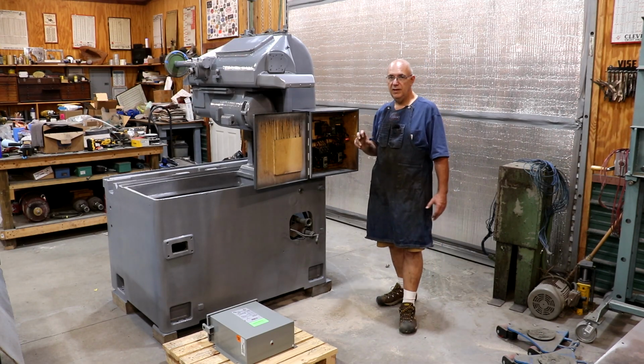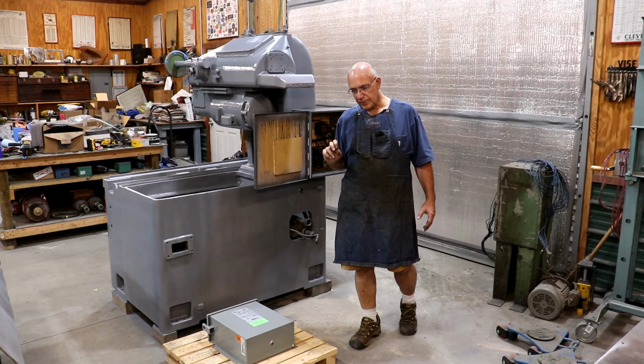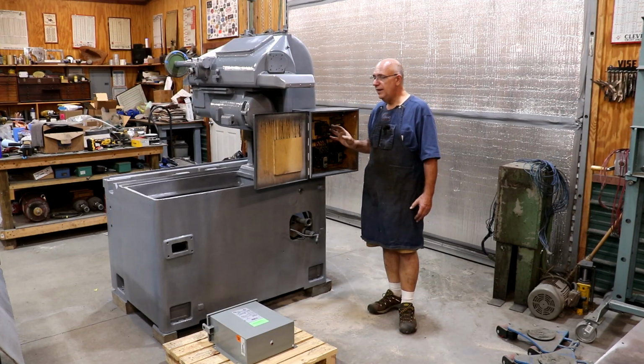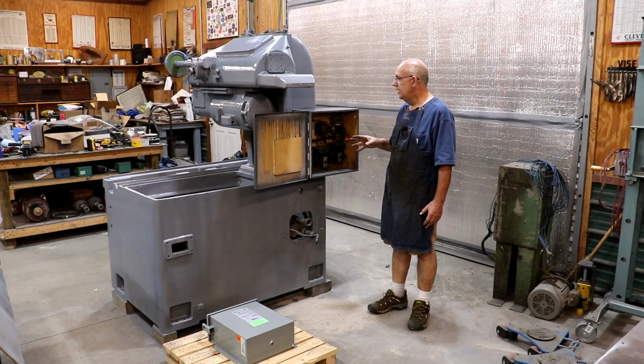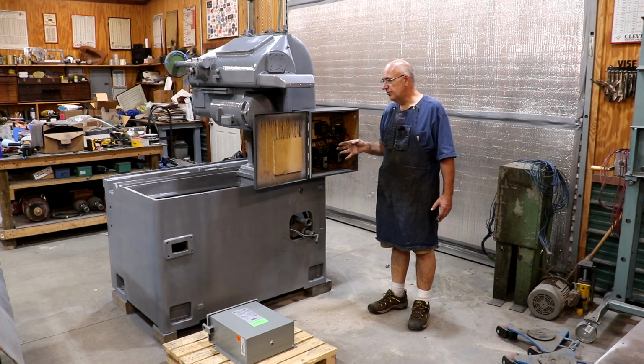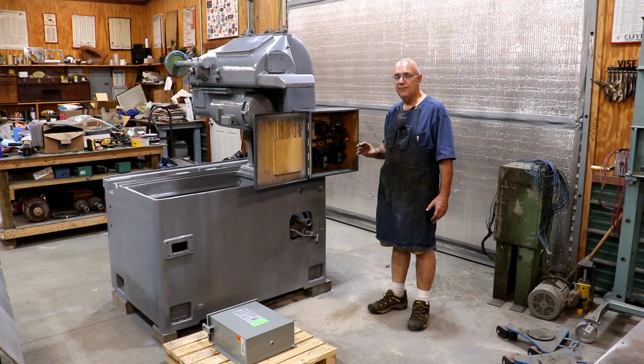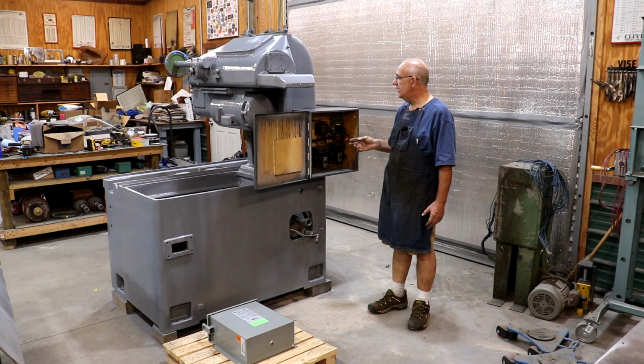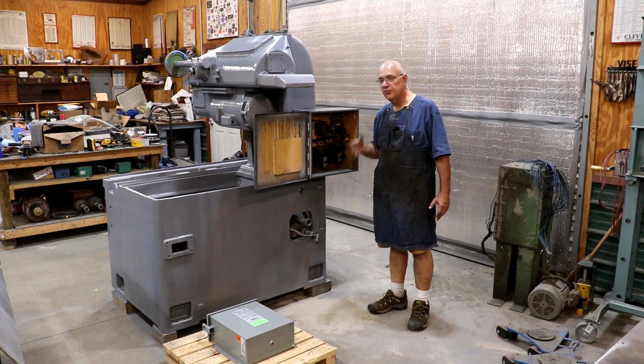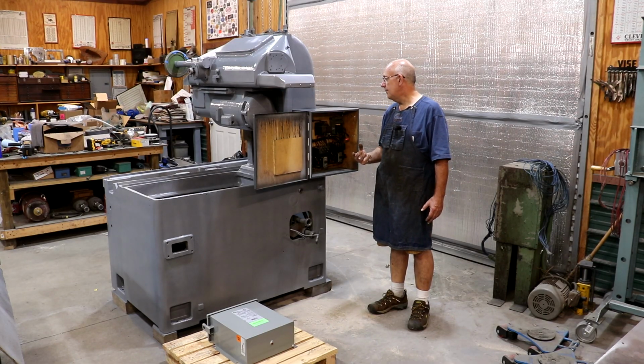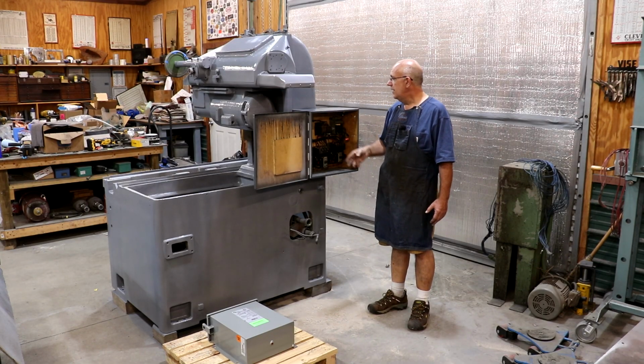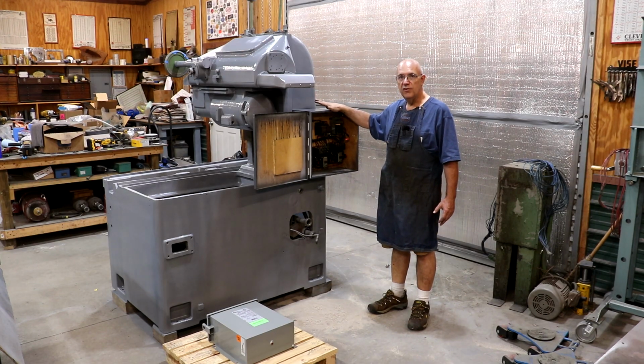First thing I've got to tackle is that this machine, as delivered from the factory, was wired for 440 volts. Now, my shop here has a rotary phase converter powering it, and I'm running 220 volts three-phase off of my phase converter. Again, this was wired for 440 volts.